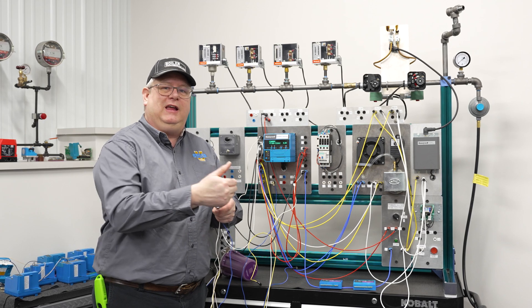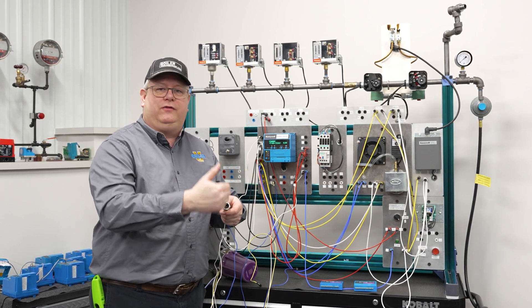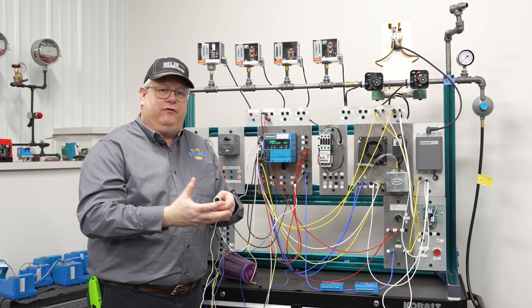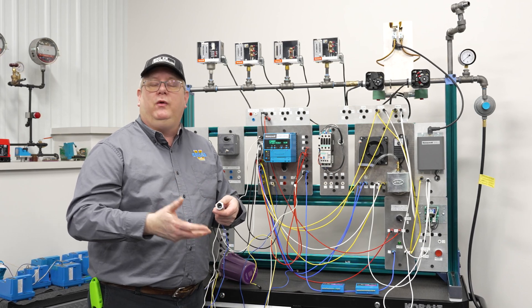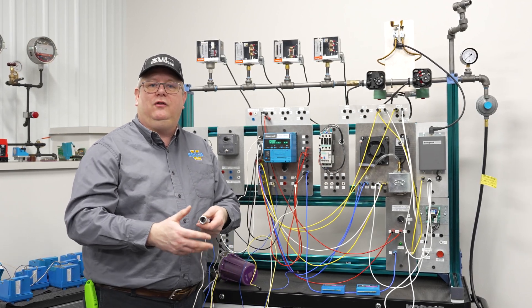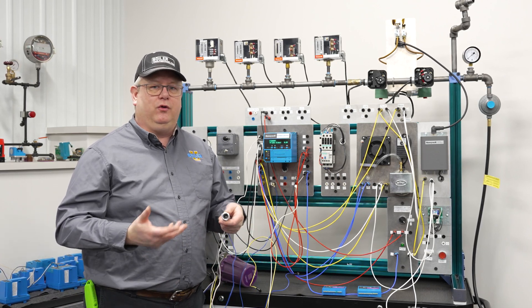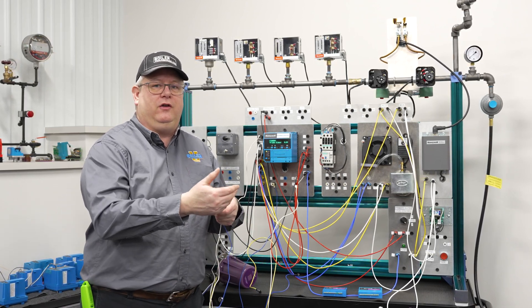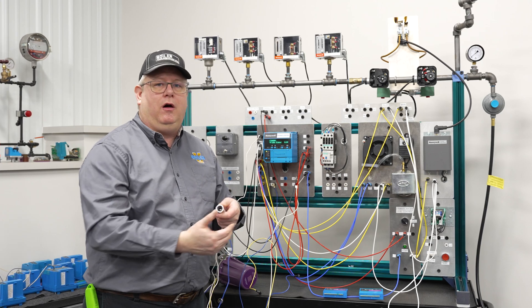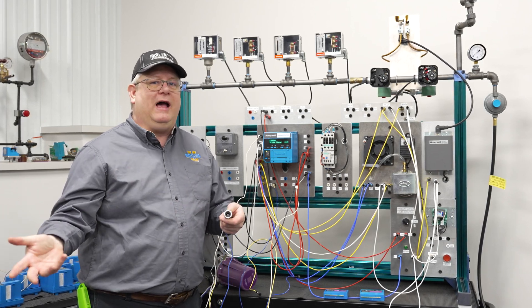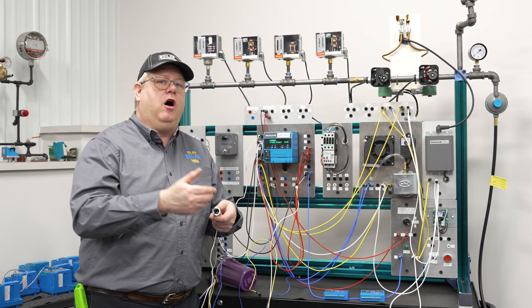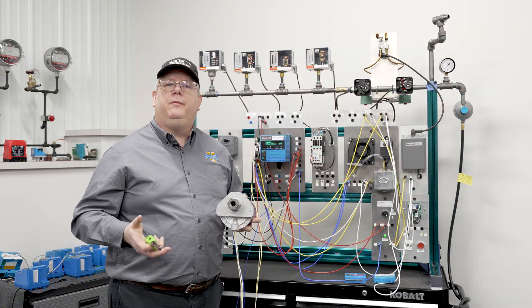If the scanner continues to detect flame through self-activation or failure of the bulb, then we can have a situation where the boiler continues to maintain the energized position of the fuel valves despite the fact that there's no combustion going on. That's going to allow gas accumulation and cause failure.